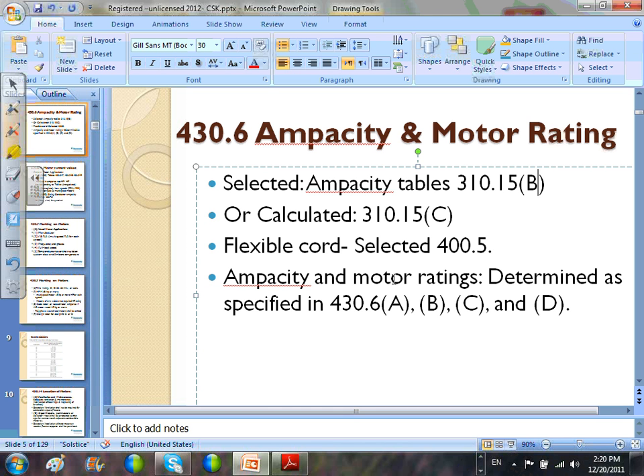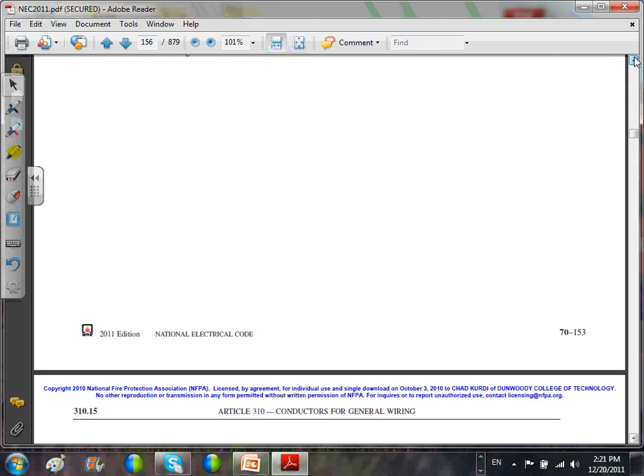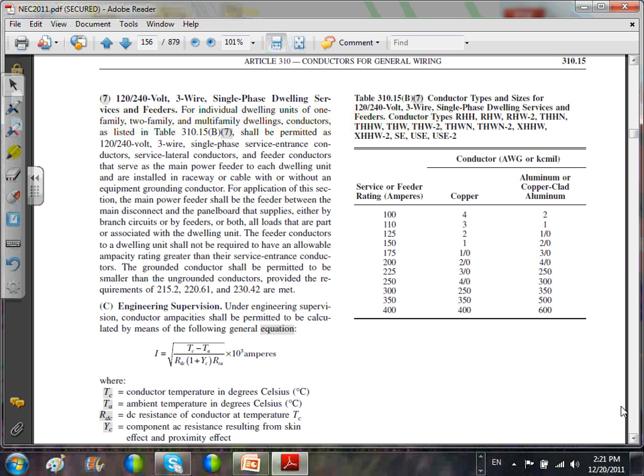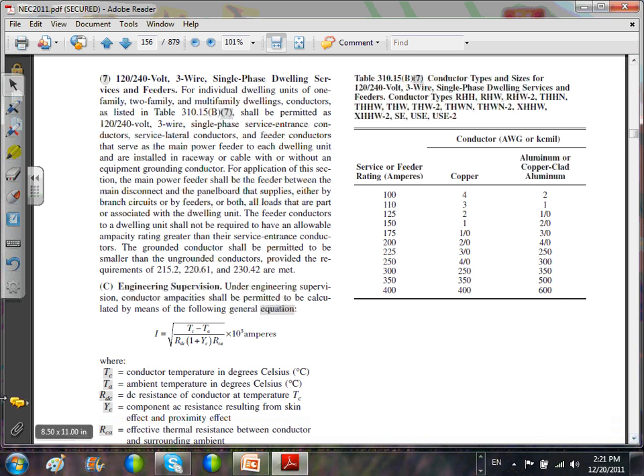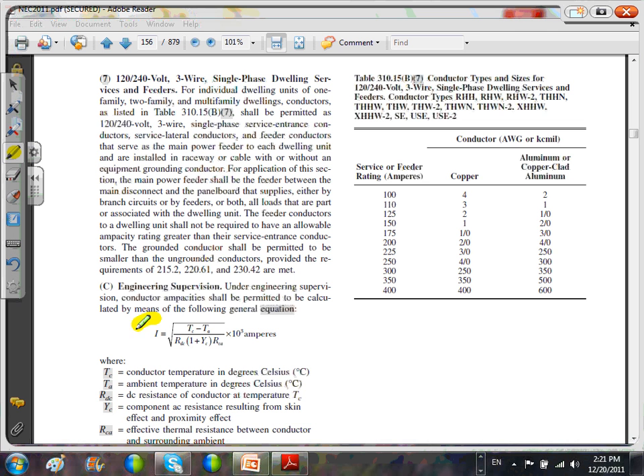Any one of you guys work on medium voltage equipment here? Raise your hand. Medium voltage, like higher than 600 volt? No? Okay. Unless you work on higher than 600 volt, 95% of the time you're going to be in 310.15. Or if you have an engineering department and when you become a master, you can calculate the amps yourself. You can do the calculation for the amps. I always like to throw 310.16 here and go back one step. If you don't like these tables, under engineering supervision, right in here, 310.15C is permitted to calculate the ampacity. Conductors shall be permitted to be calculated at this formula. So take this home, put it in your computer and size based on this formula.